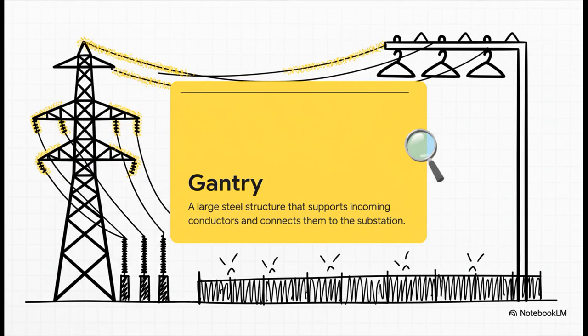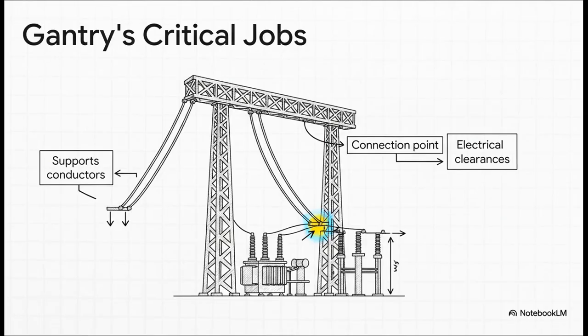So how do you get all that power from a wire dangling way up in the air down to the ground safely? You use a gantry. This is basically the first thing the electricity meets once it's inside the fence, like a giant, super sturdy coat rack for high-voltage wires. But a gantry is way more than just a simple frame. It's holding up immense tension, and it's the main connection point. Most importantly, it maintains what engineers call electrical clearances, the minimum safe distance you need to prevent that powerful electricity from literally jumping or arcing between wires or down to the ground. Very important stuff.